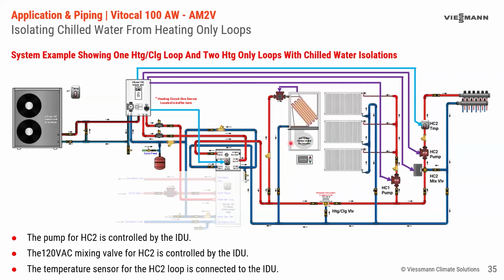Now, if we add the heat circuit 2, we have these two systems running at the same set point for circuit 1, and we have this system running at its different set point with a heating curve. The mixing valve can turn down the higher water temperature that we're obviously going to see for these two systems. And the pump then is going to be running through here, and this sensor, that's heat cool circuit sensor 2.